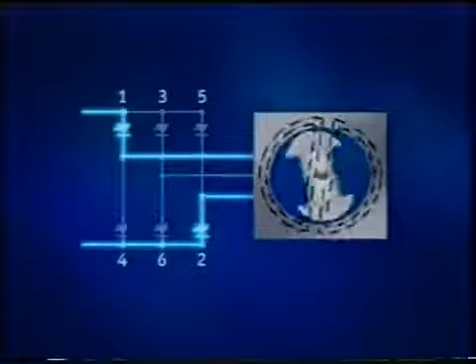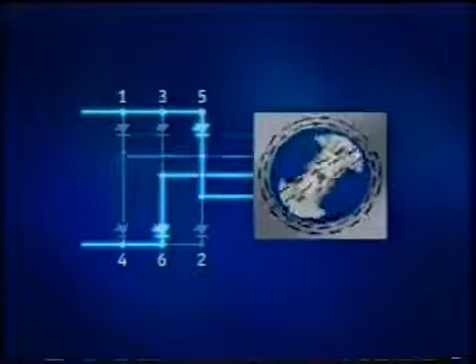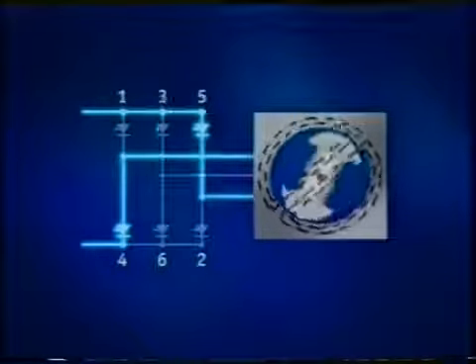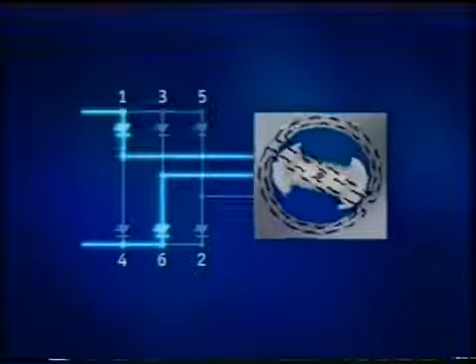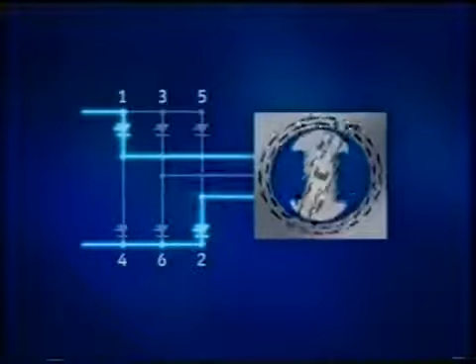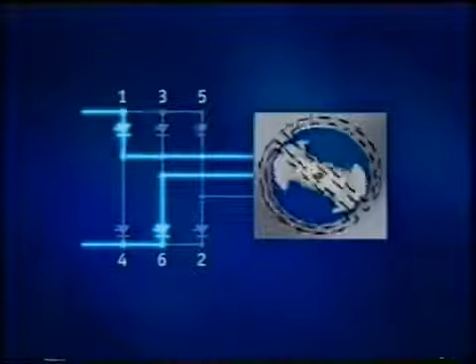At normal speed, a synchronous motor produces an internal back EMF in the stator windings which acts to automatically assist commutation of the inverter thyristors. However, at very low shaft speeds, 10% of normal or less, the back EMF generated is too low for this purpose. In these circumstances, the thyristors on the network bridge are switched to briefly suppress the current in the DC link, allowing the machine bridge thyristors to turn off and regain control.